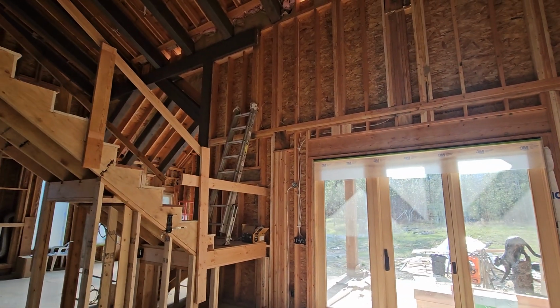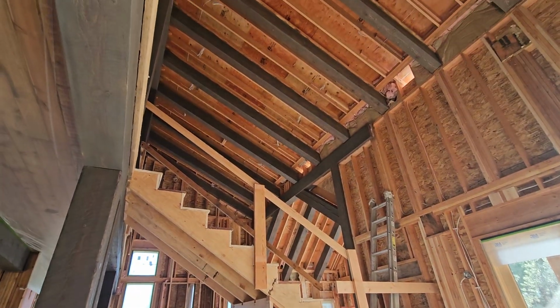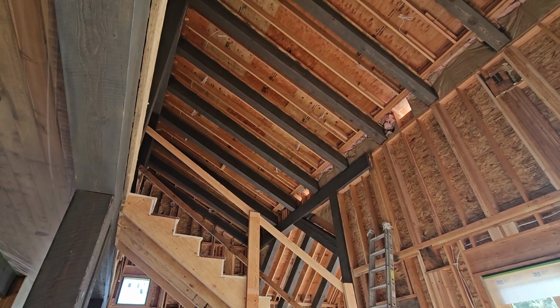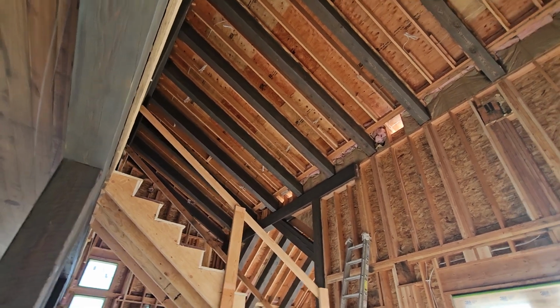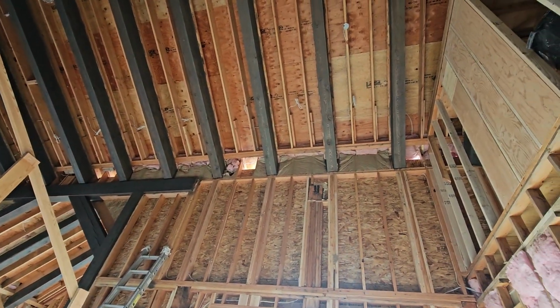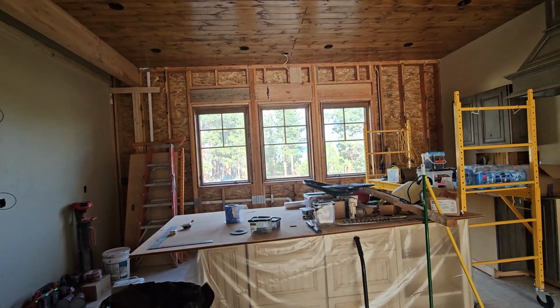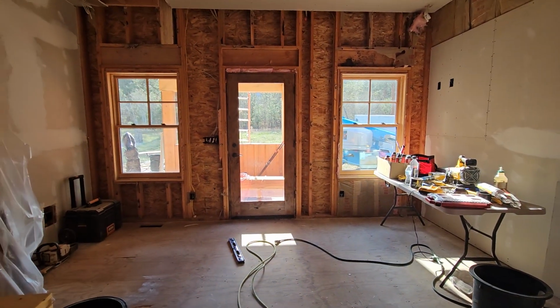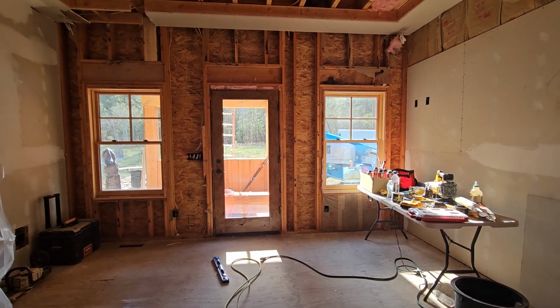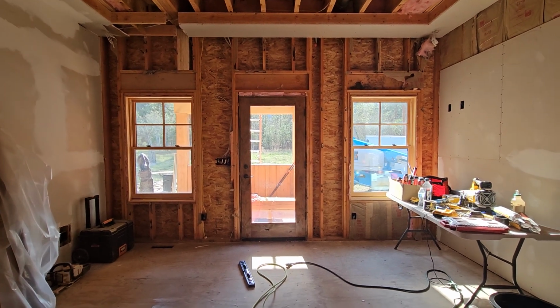And this house, the way that it's constructed, really kind of needs the foam insulation. You can see they had to pull out a lot of lights in the ceiling. There was not adequate space to insulate the roof behind those can lights that were up here. The foam is about the only way to really go on this roof and get adequate insulation, because you cannot squish batt insulation like it was and get the result you want. It defeats your purpose. It ruins your R value. It wrecks the insulation. And even then, on these outside walls, we did not have enough space. We didn't have enough insulation. And in the long run, you hate to build this kind of house and not have adequate insulation.